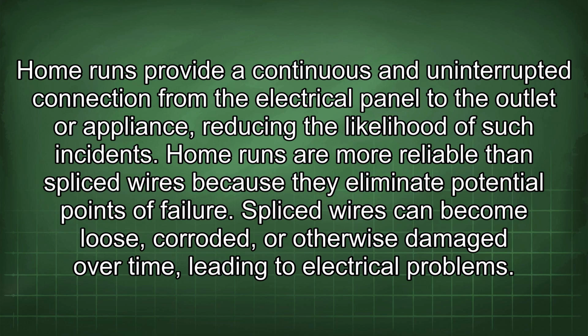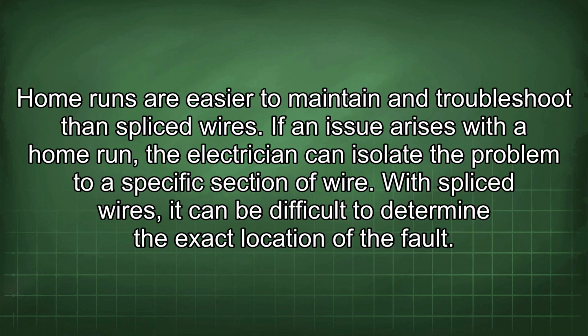Spliced wires can become loose, corroded, or otherwise damaged over time, leading to electrical problems. Home runs are easier to maintain and troubleshoot than spliced wires. If an issue arises with a home run, the electrician can isolate the problem to a specific section of wire. With spliced wires, it can be difficult to determine the exact location of the fault.